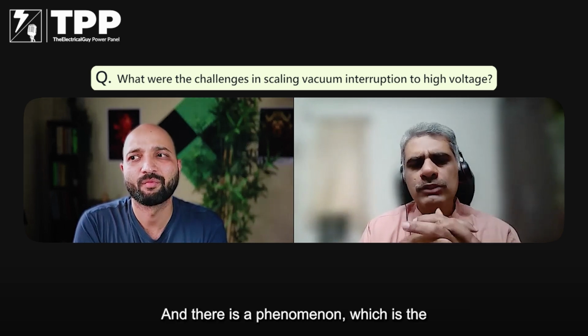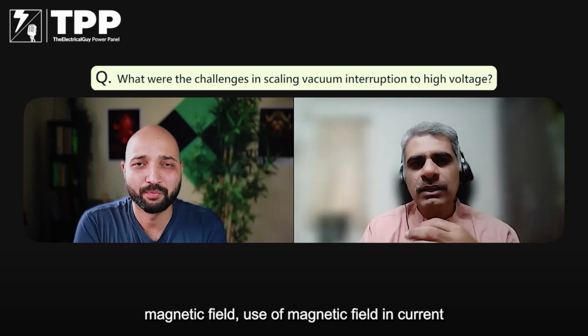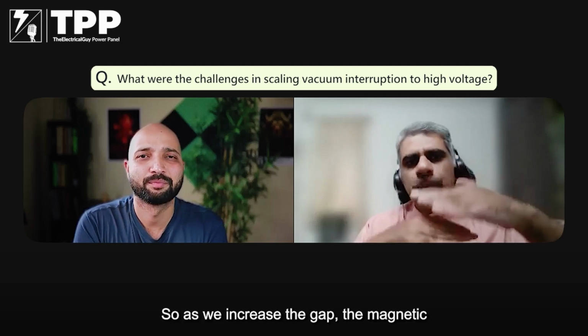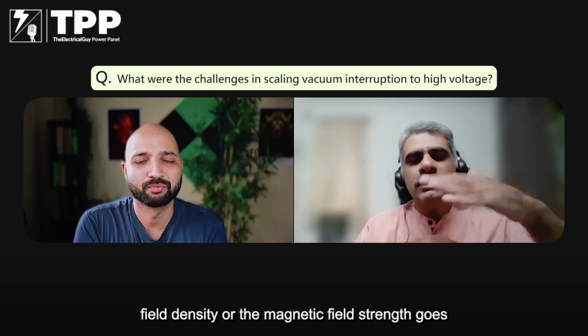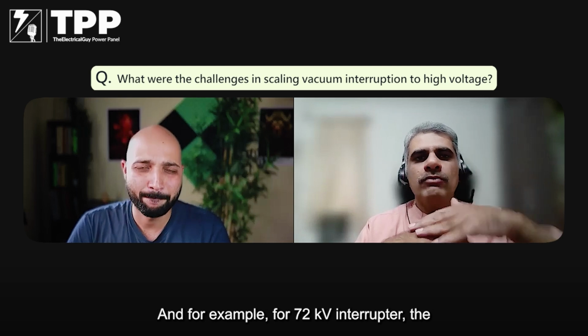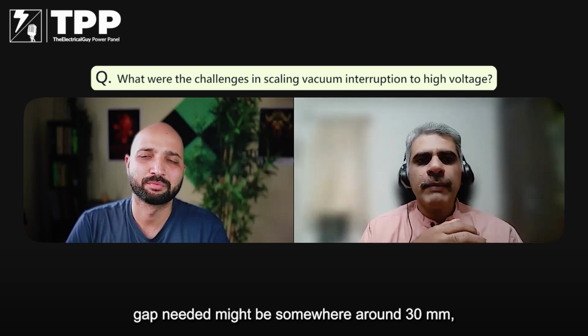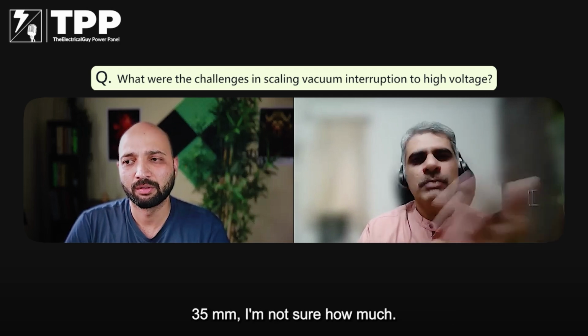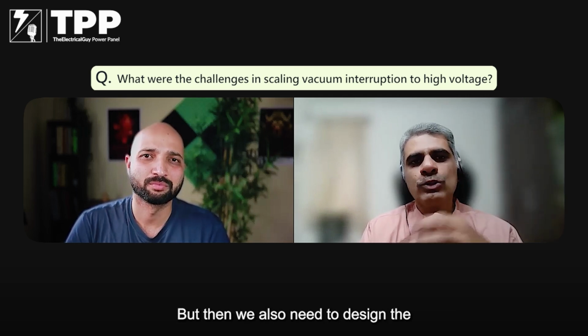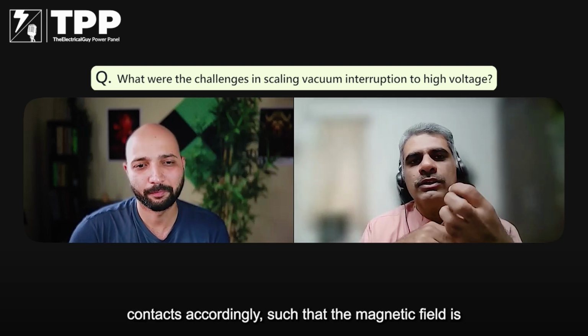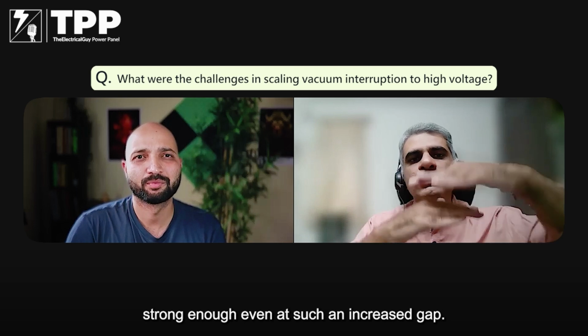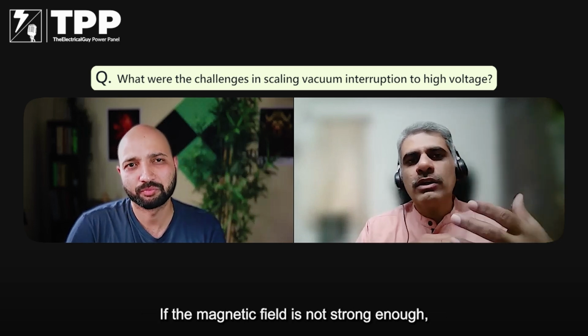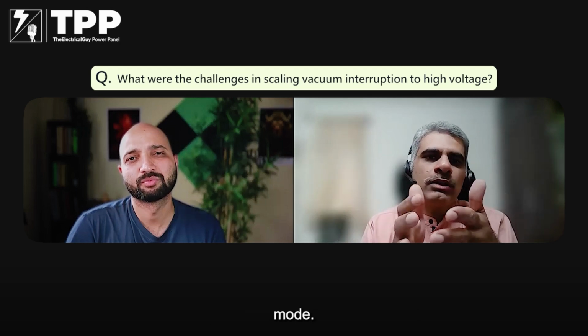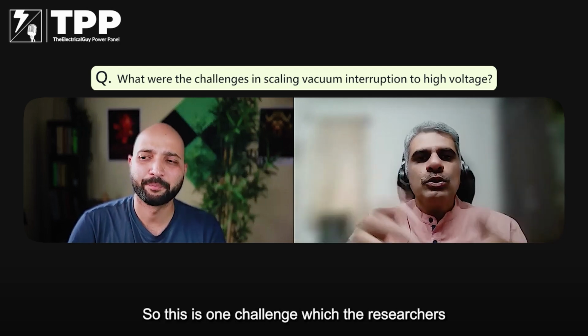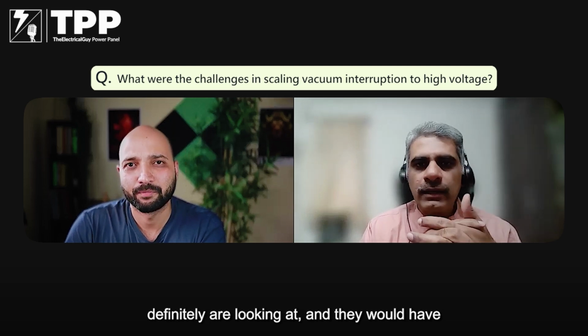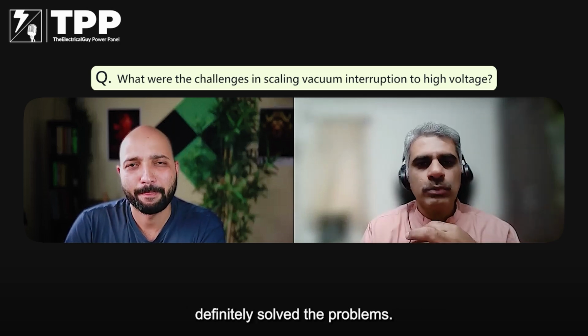And there is one phenomenon I touched upon, the use of magnetic field in current interruption. As we increase the gap, the magnetic field strength goes on reducing. For example, for a 72 kV interrupter, the gap needed might be somewhere around 30 or 35 mm, I'm not sure how much. But then we also need to design the contacts accordingly such that the magnetic field is strong enough even at such an increased gap. If the magnetic field is not strong enough, the arc will again go to its constricted mode. It may not stay in the diffuse mode. This is one challenge the researchers are looking at, and they would have definitely solved the problems.